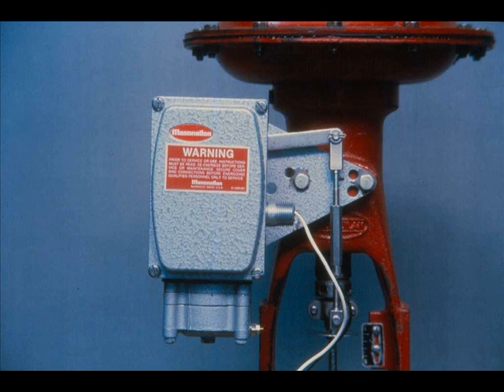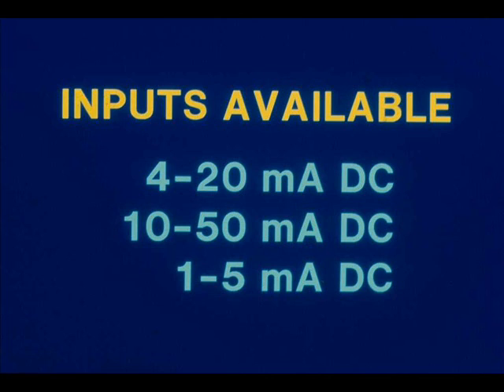The Masoneilan model 8012 is an electro-pneumatic valve positioner. It provides an accurate means of obtaining a valve stem position proportional to a 4 to 20 milliamp DC input signal. Besides the 4 to 20 milliamp input range, it is also available for input ranges of 10 to 50 milliamps and 1 to 5 milliamps.